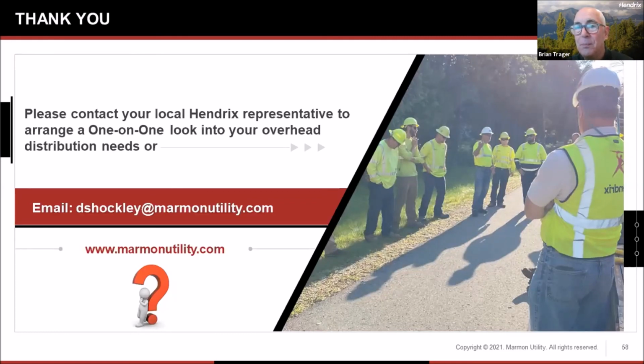Okay, are there voltage limitations for spacer cable? We're only going up to 115 kV. So again, we have every voltage class from 5 kV to 115 kV. That would be our limitation. We see getting into 138, 145, and 230. Those are the next generations, but we don't have those yet.